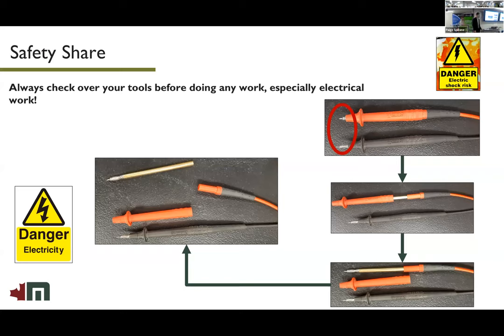One of our electricians was just about to perform a live test on a 700 volt DC bus when he noticed that his tool lead was slightly shorter on one side. He pulled the tool aside and noticed that the insulation was loose. Upon pulling on the insulation, he noticed the whole tool came apart, at the position where his finger would have been on that rib grip. So there's definitely a risk that he could have been exposed to.